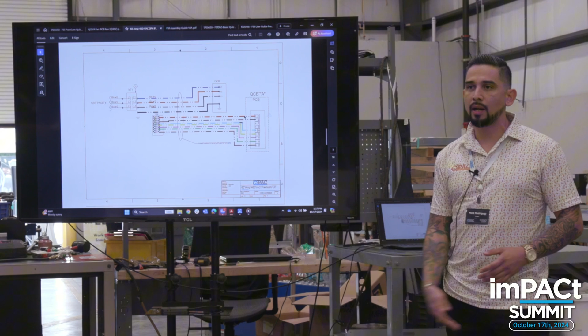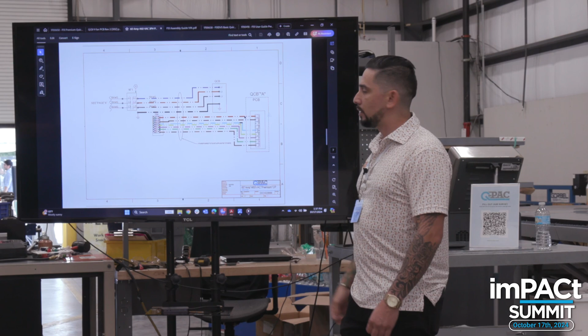You will have more than one QCB at times. If you do, you are not to daisy chain them. They have to be run on separate conduit from terminal block 8, 9, 10, or 11 to QCB A, B, C, or D. I've had instances where people daisy chain from A to B thinking that's okay, but then you'll get a ton of alarms.